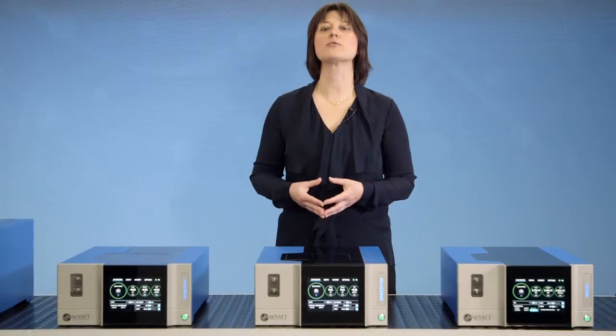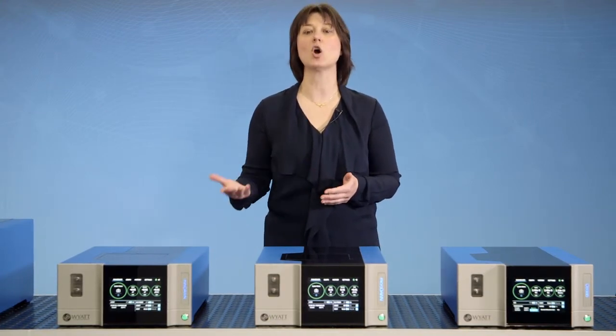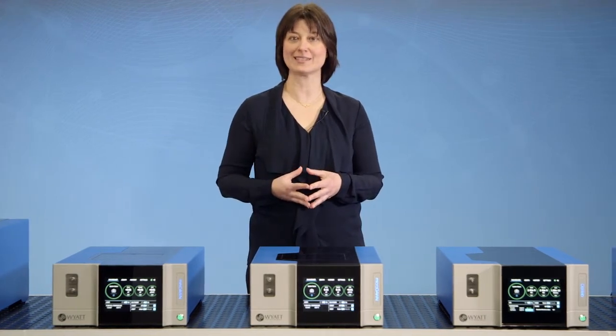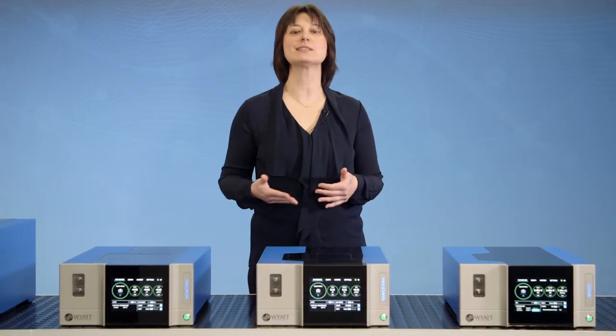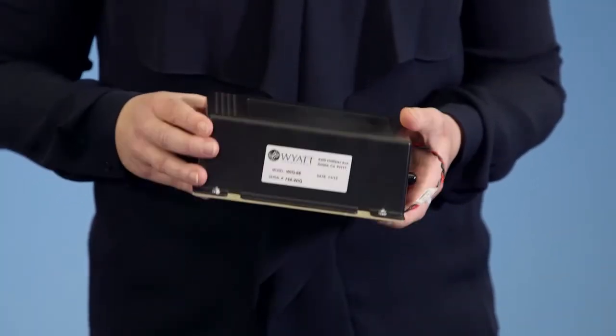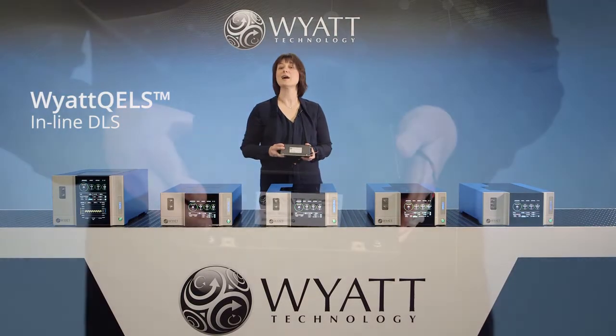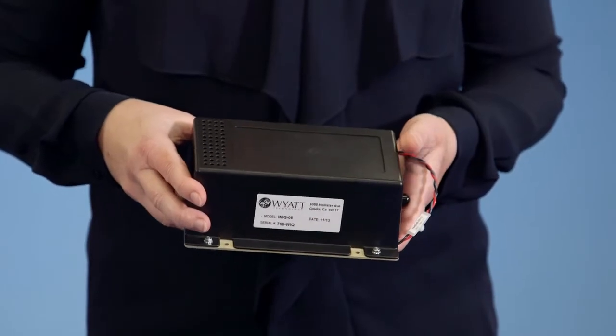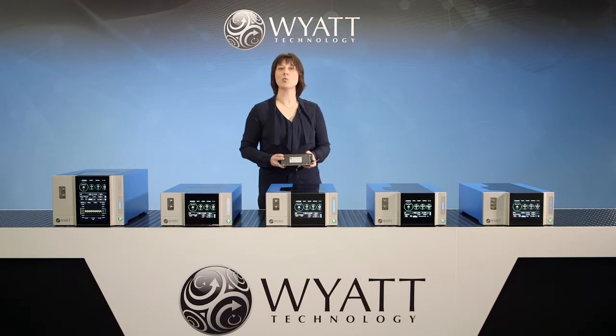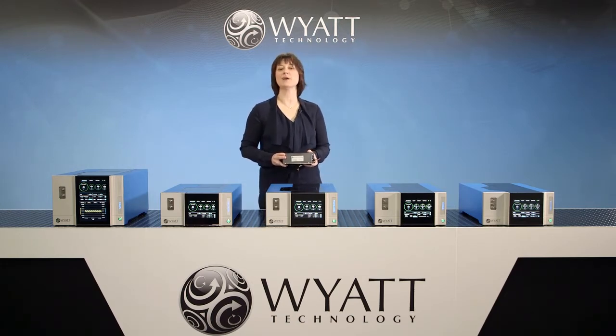You also have the option of combining online dynamic light scattering, or DLS, with any Dawn, Mini Dawn, or Micro Dawn instrument when you need to determine hydrodynamic size, which is highly desirable in proteins and other biologics applications. This can be done by simply embedding our WyattQELS DLS module inside of any of our MALS instruments. Alternatively, it's possible to externally connect one of our standard stand-alone DLS instruments via a fiber optic cable.